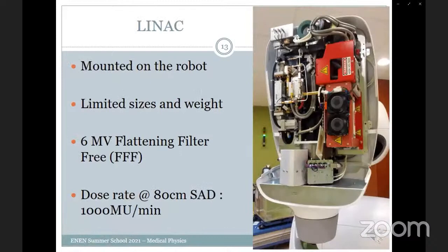If we remove the cover of the linear accelerator, we can see this. You can see in the middle there is the accelerator tube. On the right side you can see the magnetron and high voltage, the boost transformers and so on. So they had to fit all these things into a very small volume, and they had to keep the weight of this head below 350 kilograms because the robot cannot handle more weight.